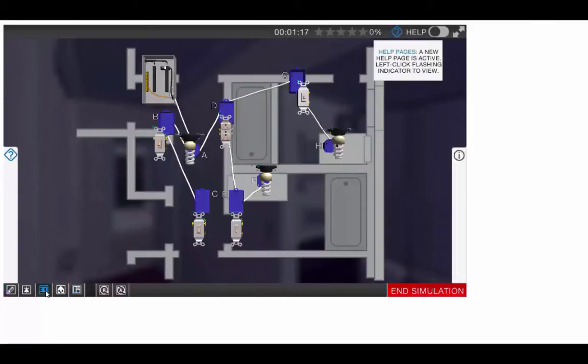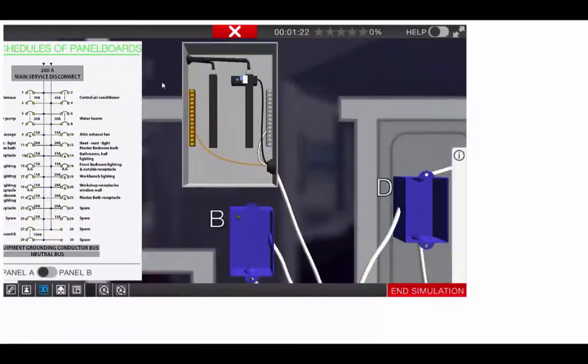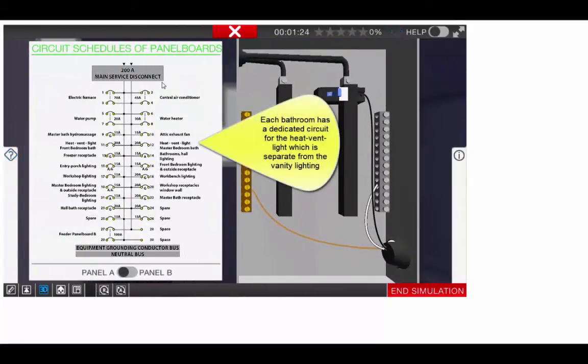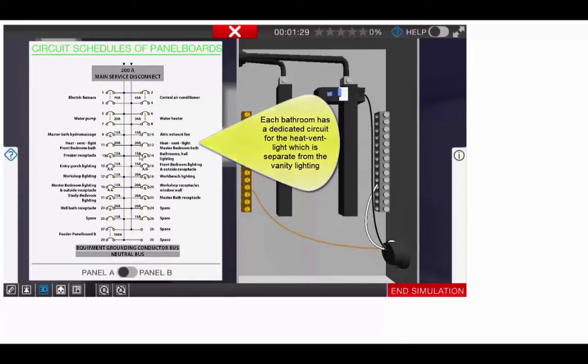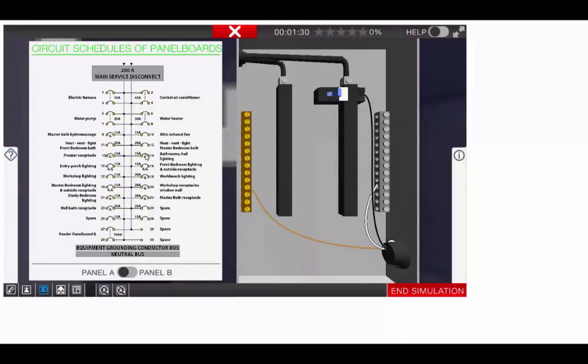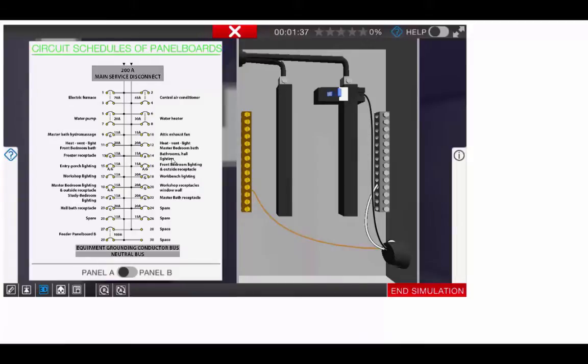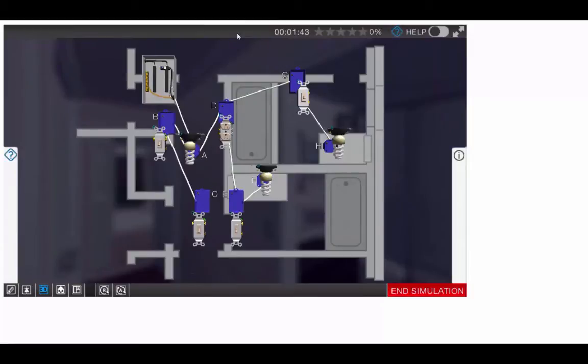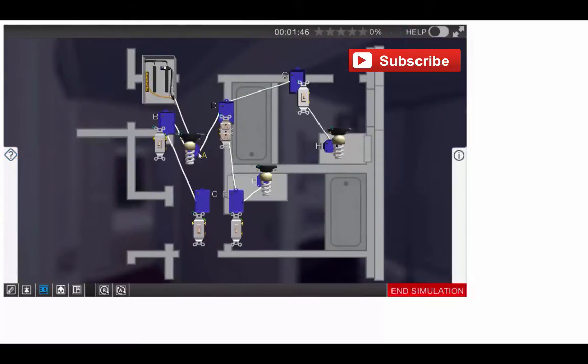So as we come into the main 3D simulation, we'll click on the electrical panel. It brings up the circuit diagram. We'll be working on circuit A14 today, which is a 15 amp circuit. It is an AFCI circuit because of the hall lighting and the outlet. Bathrooms do not require an AFCI circuit. So to get started today, we notice that our home run is coming to box A. So we will populate our wires now for the project.